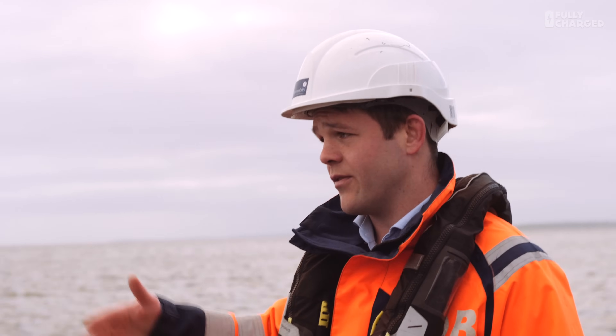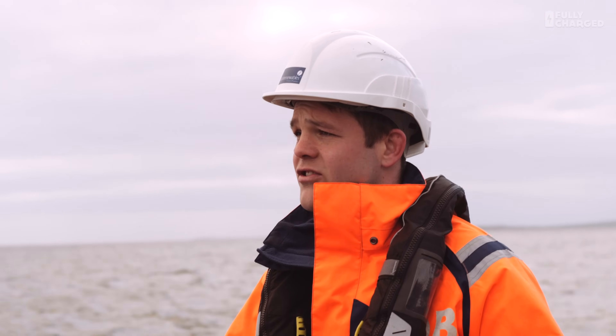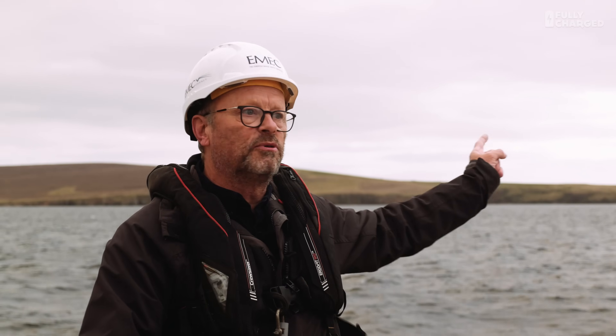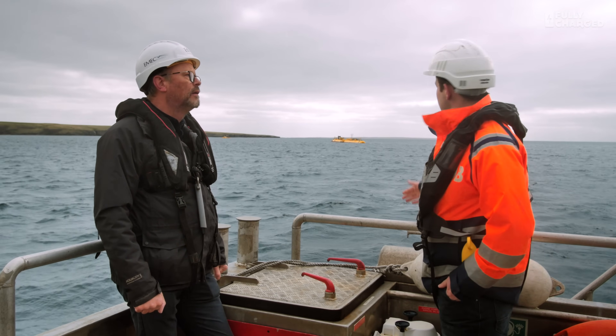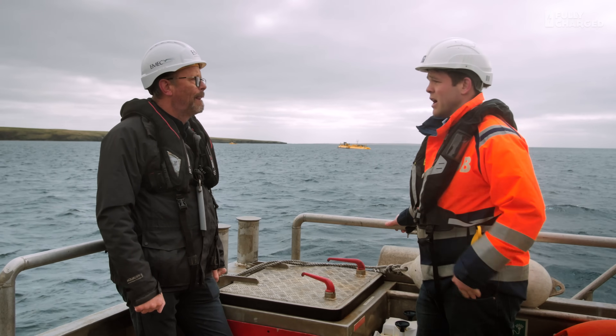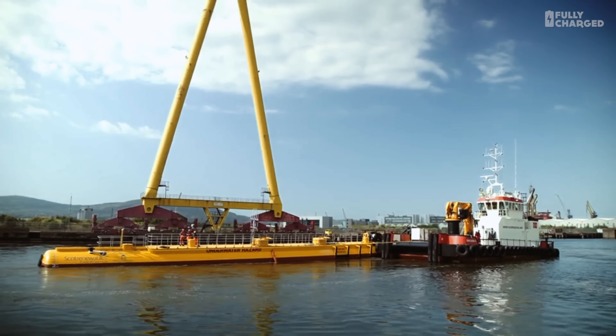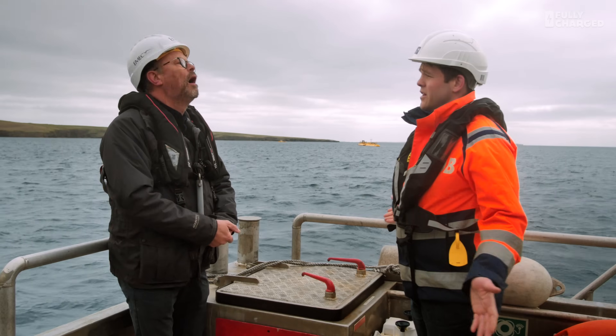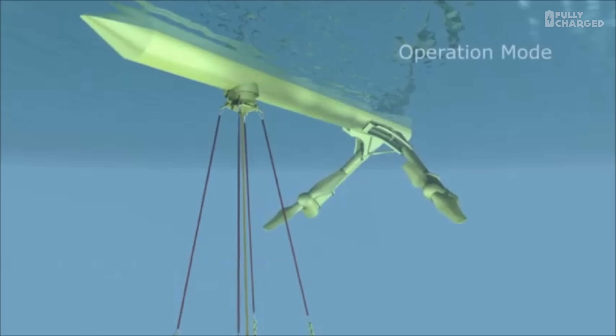Ahead of this device, engineers are developing a new turbine — the Flow Tech project. As for going bigger, two megawatts is a sizable turbine, but we're still looking at reducing the levelized cost of electricity and making maintenance easier. One advantage of the floating design is you can do maintenance on it easily. A team can go out on a RIB, access the turbine for diagnostics, then tow it on and off site with locally available workboats and multi-cat vessels — no need for huge dynamic positioning cranes. The legs are retractable, so you can put it into survivability or transportation mode to reduce draft.